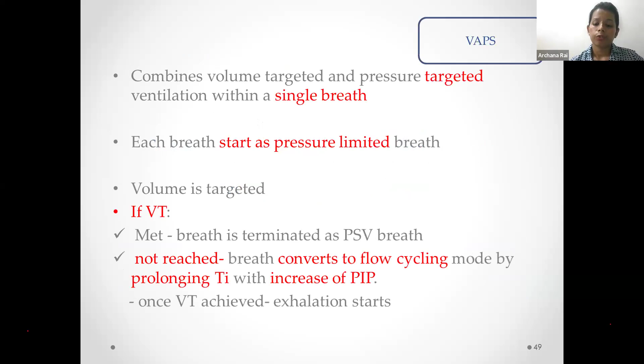Another mode is VAPS mode. What is VAPS? Volume assured pressure support mode. In this, the first breath is given as a pressure breath, and it will see whether we have achieved the tidal volume or not. If we have achieved the tidal volume, it will end the inspiration and go into expiration. But in some cases, if the compliance is decreasing or resistance is increasing, once the pressure has been generated but the tidal volume has not been achieved, this mode will help in achieving the tidal volume.